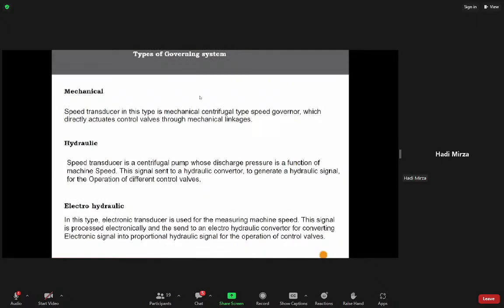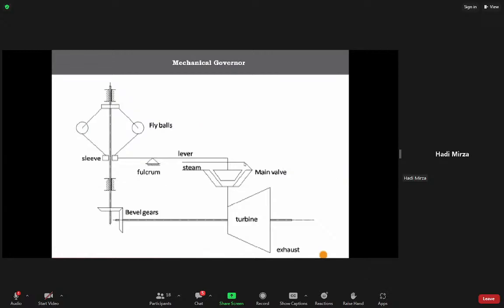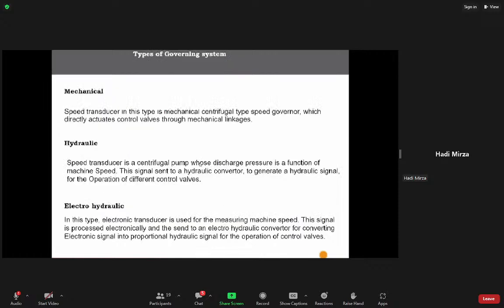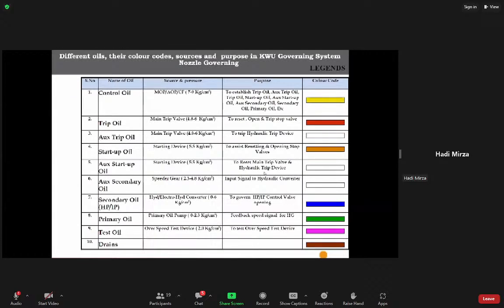Types of governing system. Mechanical governing system basically takes the input from the speed of the turbine, and then mechanical as a speed transmitter. If you see the BHEL-made turbines, the MOP gives a primary oil pressure. That pressure acts as a speed sensor, an indirect type of speed sensor. This primary oil pressure is taken as the speed signal and generates the hydraulic signal, and operation of control valves will be done. We'll see how it works in the hydraulic type of governor.